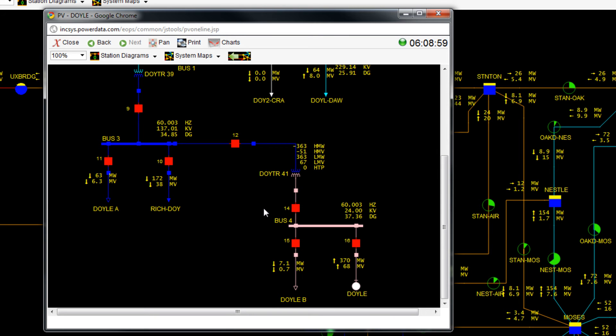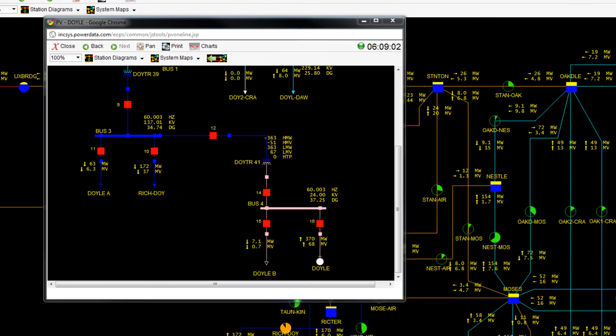This should keep frequency steady at 60 Hz. Now since the ramp rate is at 40 MW per minute, this redispatch will take around one and a half minutes.